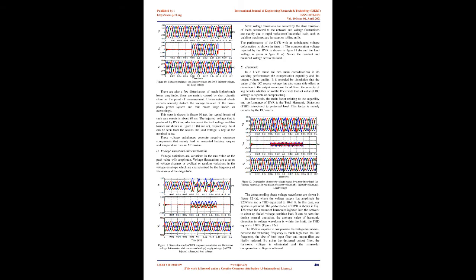Figure 6A shows that a 25% voltage sag is initiated at 0.08 s and kept until 0.16 s. Figure 6B shows the injection voltages produced by the DVR in order to inject the missing voltages, due to the balanced fault, into the supply voltages, and Figure 6C shows the compensated load voltage. As a result of DVR use, the load voltage is kept at 220 VRMS throughout the simulation, including the voltage sag period. One can observe that during normal operation, the DVR is doing nothing. It quickly injects the necessary voltage components to smooth the load voltage upon detecting a voltage sag.